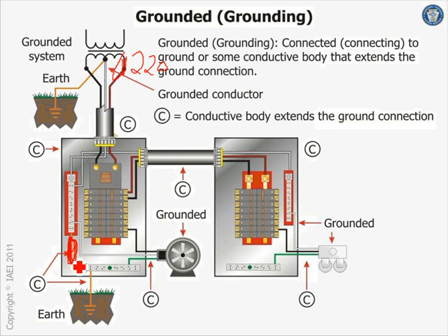At that level, when you have apartment, industrial, commercial, when you have multiple loads coming together and you lose a neutral, there is enough load in the building to balance it between the three phases that you wouldn't burn. It would act wacko though. The lights go up and down, but there is enough load balance not to burn the building. Put it this way, still, you want to solve the problem, shut down the system. Any comments? Any questions? Comments, guys?